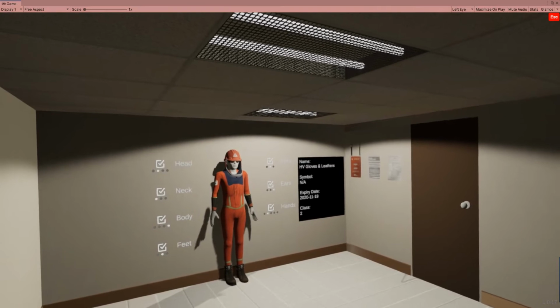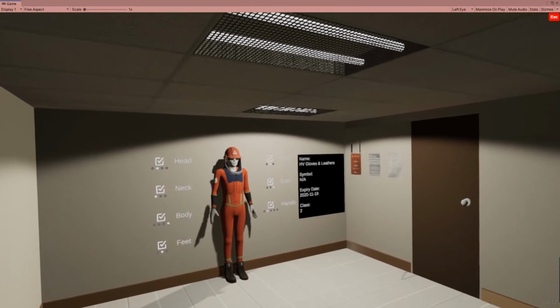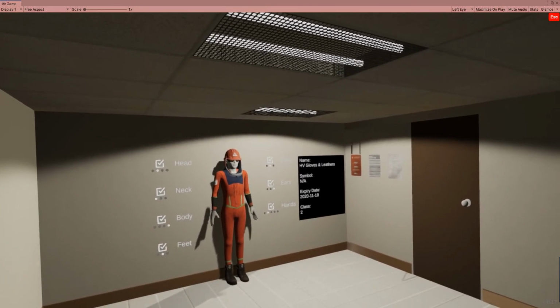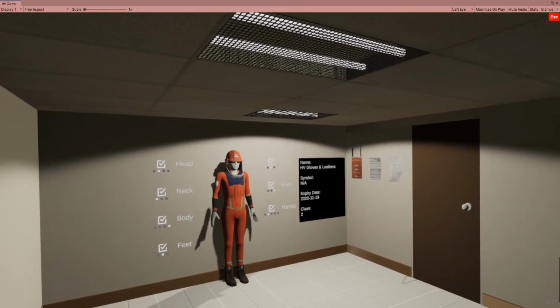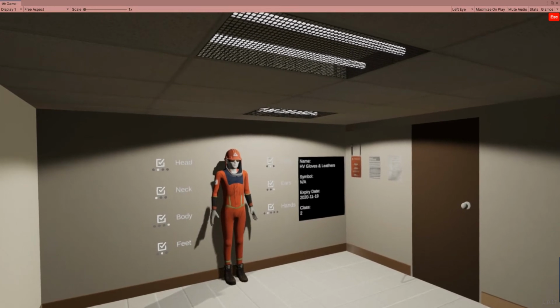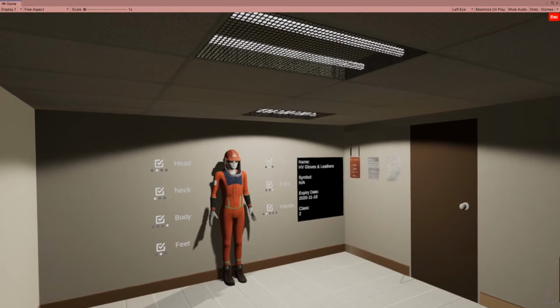Before performing any switching activities, you need to make sure you have the required switching order, permit, and employee in charge, or EIC, sign. This must be reviewed with all the applicable personnel before being implemented. Obtain the correct permit from the appropriate permit center prior to the start of any switching activities.